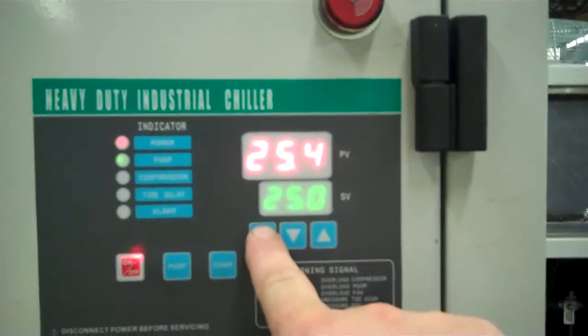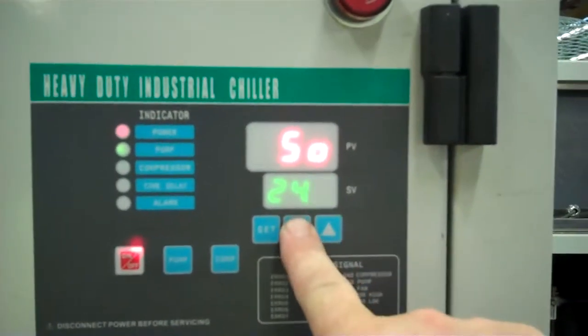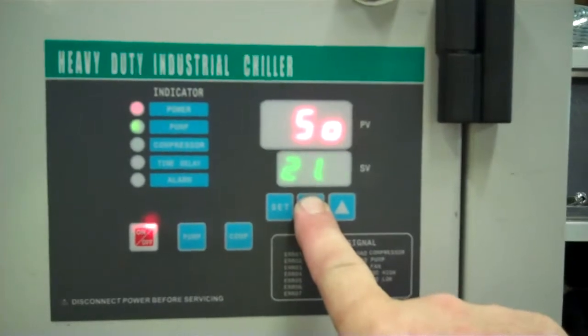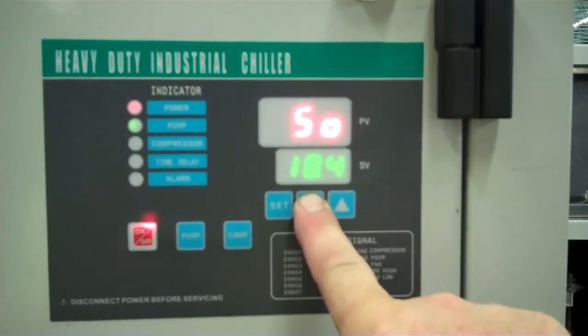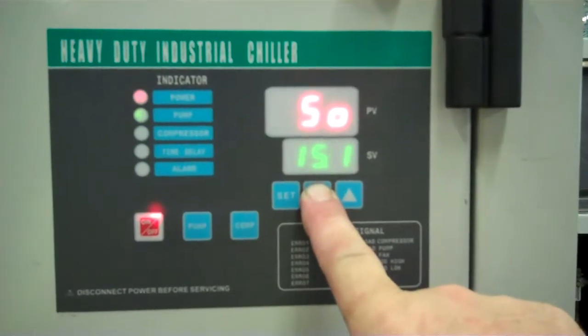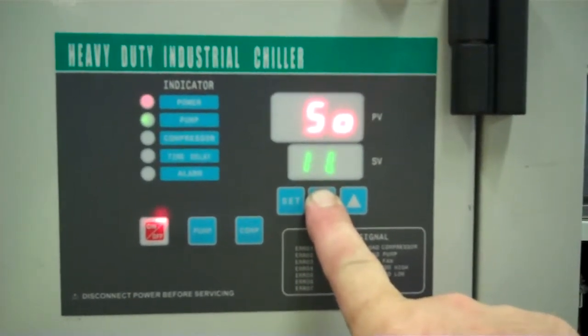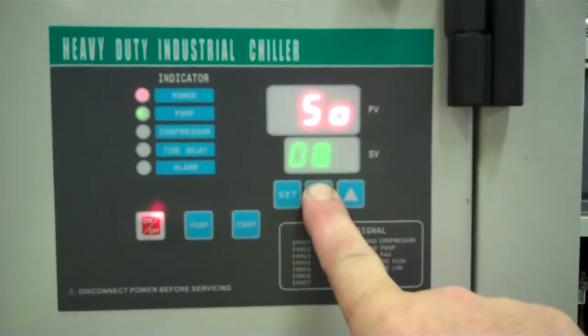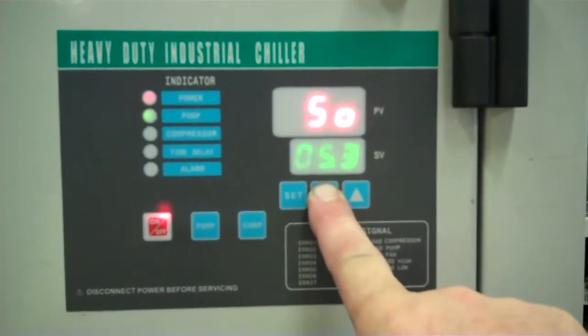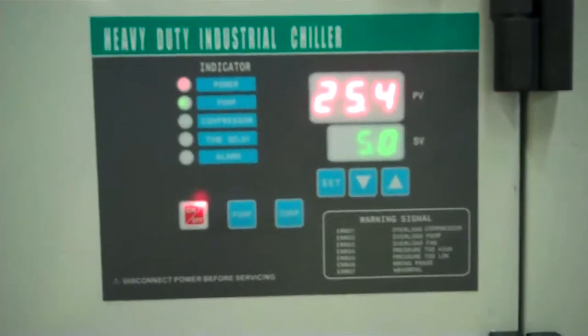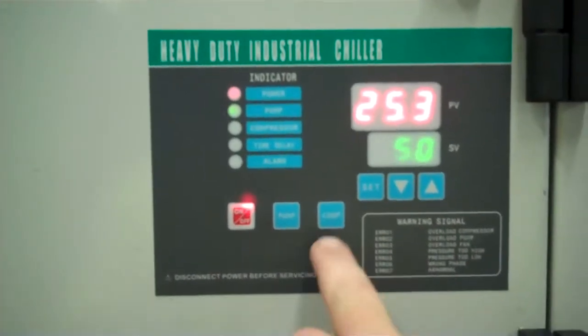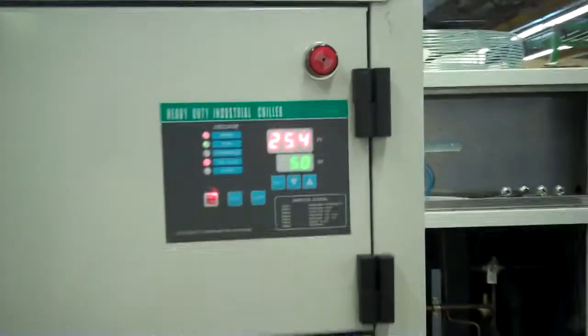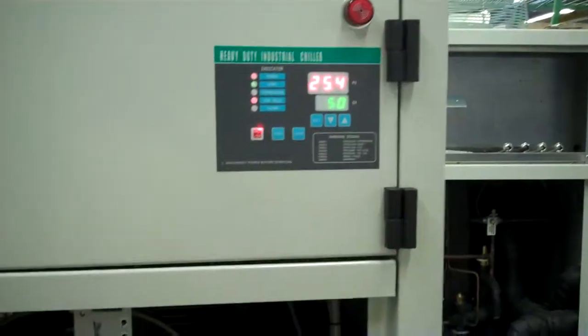And we're going to change the set point by pressing set. And we're going to chill it all the way down to 5C. 5C is about 41 degrees Fahrenheit, give or take a little bit. Okay, so there's a set point there. Now, to start it, we got to turn the compressor on. Now, you'll notice when I press that, the time delay comes on. That's a built-in safety into the controller. It might take about 90 seconds for the system to kick on and start cooling.